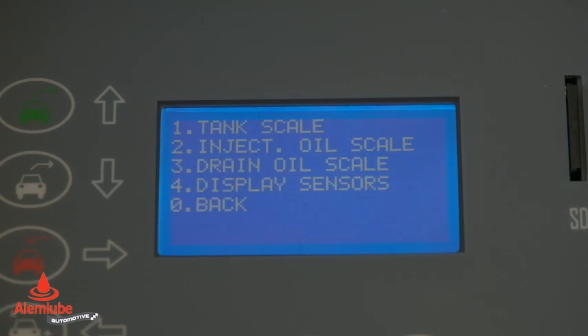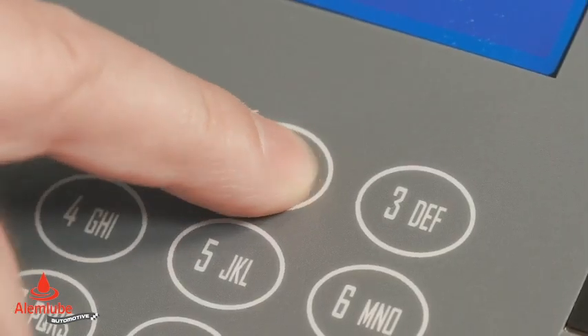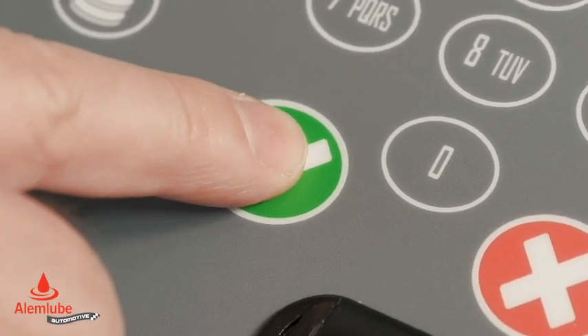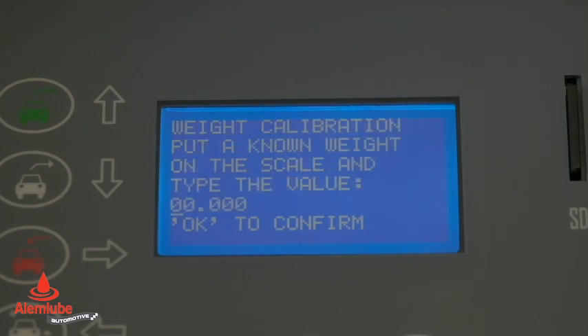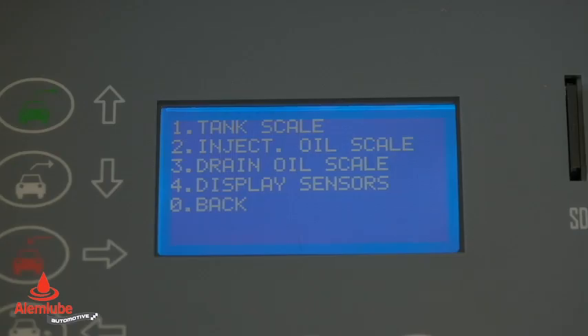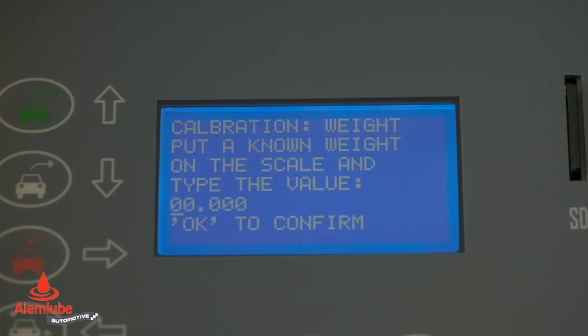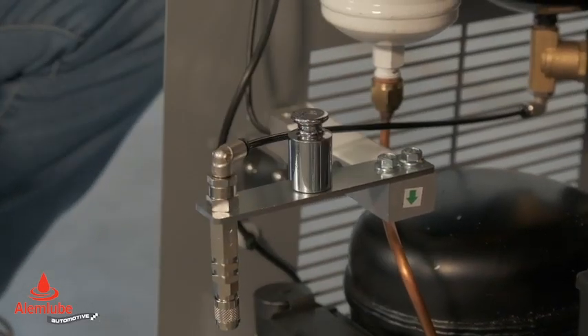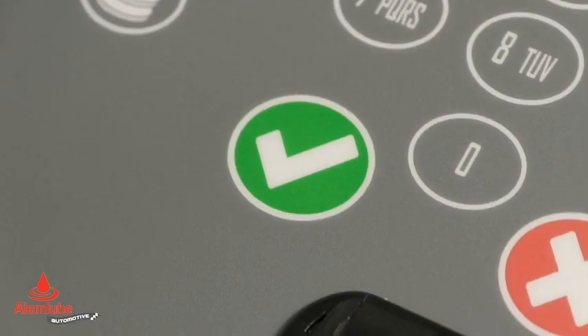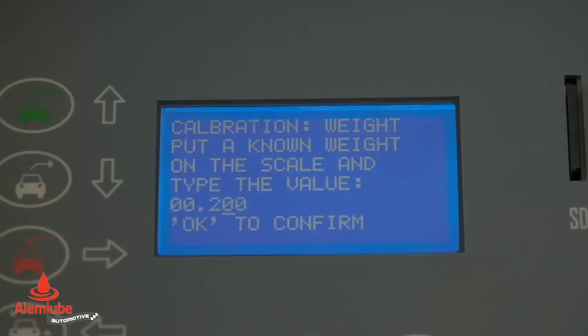In the same way, we can proceed to the calibration of the oil scales. Select 2 to start the calibration of the oil injection scale. Press enter to store the 0 value with the scale empty. Apply a sample weight, for example 200 grams, to the scale. Type 200 grams on the display and press enter to store the second calibration point. Now we can proceed to the calibration of the oil discharge balance. Select 3 to start the calibration of the oil discharge scale. Press enter to store the 0 value with the scale empty. Apply a sample weight, for example 200 grams, to the scale. Type 200 grams on the display and press enter to store the second calibration point. All scales are now calibrated.